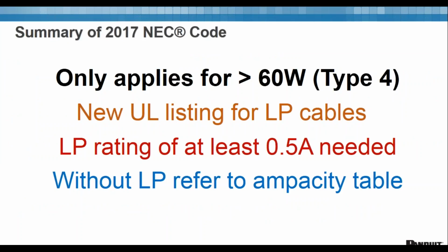So, summary: the 2017 NEC only applies for greater than 60 watts, the new Type 4. There's a new UL listing for LP cables. You will need an LP rating of at least 0.5 amps or higher, and without LP, refer to the ampacity table.